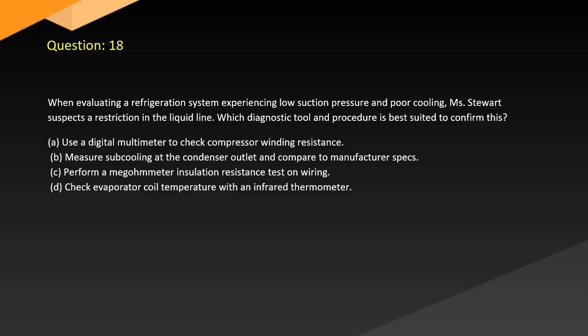Question 18. When evaluating a refrigeration system experiencing low suction pressure and poor cooling, Stewart suspects a restriction in the liquid line. Which diagnostic tool and procedure is best suited to confirm this? A. Use a digital multimeter to check compressor winding resistance. B. Measure subcooling at the condenser outlet and compare to manufacturer specs. C. Perform a megohmmeter insulation resistance test on wiring. D. Check evaporator coil temperature with an infrared thermometer.